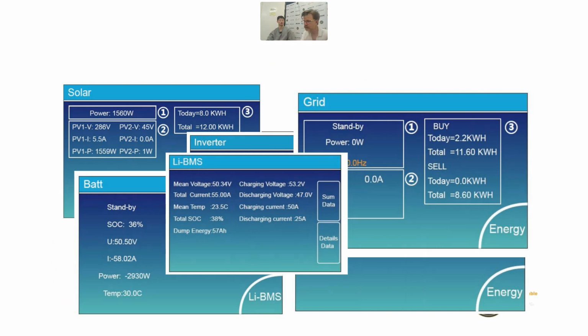Click on Li-BMS and you'll see this box in the middle. If the battery is communicating with the inverter, all these values will be populated like you can see here. If they're all blank, it means it's not getting data from the battery. So if it was, say, Pylontech, you'd check that the cable was plugged into the CAN port and not one of the others, and check the battery is on.